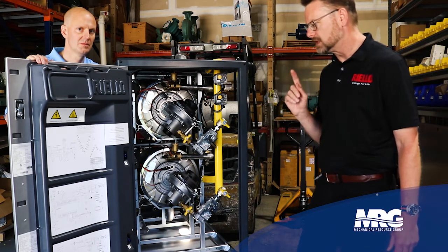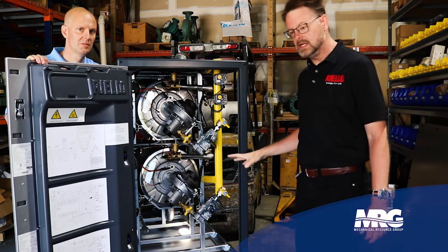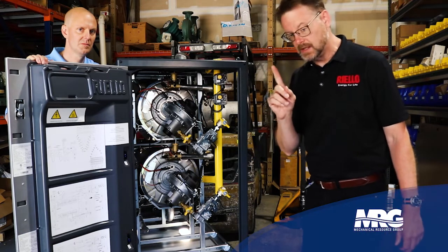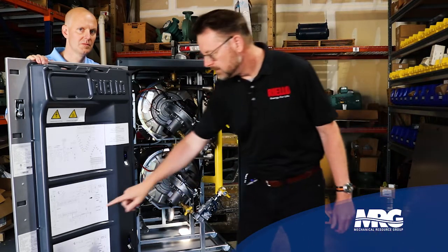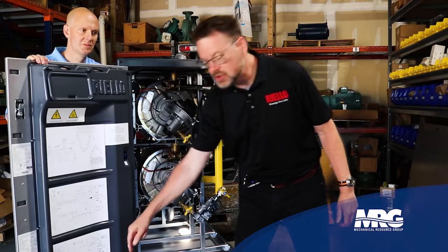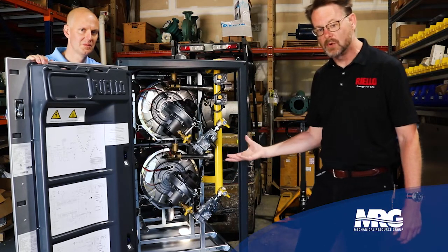There are some controls and safety devices in the cabinet that are common to all the heat engines. The trick, if you have nothing else to do one evening, is to download the installation and operation manual and look at the wiring differences between the managing controller and the dependent controllers. You'll see there are some controls and safety devices that land on the managing controller. The managing controller then doles out those go signals, if you will, to the other controllers so that the other Helix heat engines know that it's safe to operate.